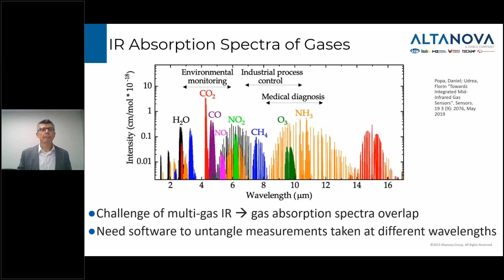So in terms of the configurations for doing the IR measurements, I'll start with what I think is probably the simplest one, and it's commonly called the non-dispersive infrared approach. Sometimes you'll hear NDIR. And it is really quite simple. You typically have a volume of the gas in a container in the shape of a tube. You have a light source at one end, and you have one or more optical detectors at the other end. And for each detector, there's a filter that allows light only from one narrow wavelength. So there's one filter-detector pair for each of the target gases we want to quantify in this application.